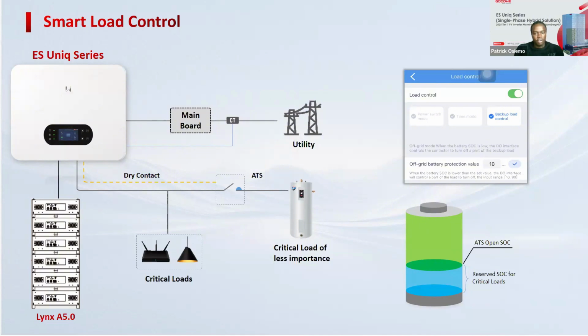The inverter comes with a dry contact, which you can use to send a dry contact signal to an ATS or even a contactor. Once your battery charge level reaches a very low point, for example 40% state of charge, the inverter can automatically send a switch-off signal to the heat pump, so that the rest of the battery charge is only drained through the most critical loads in your house. That's a smart and efficient way to use your energy and not go into a blackout in case you're running off-grid in the middle of the night.